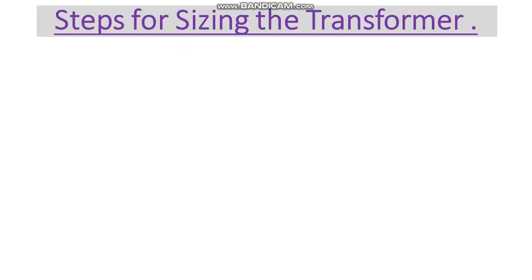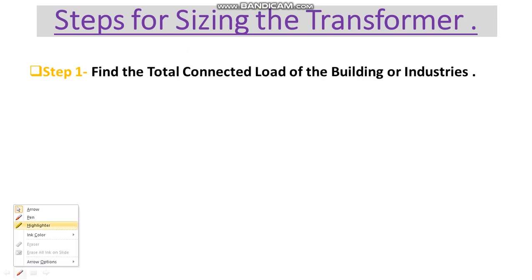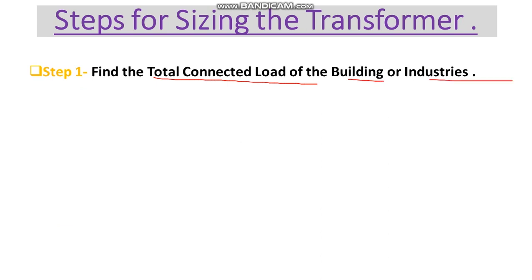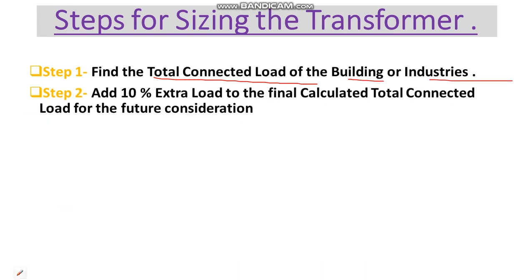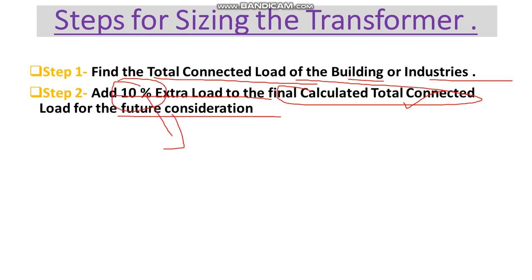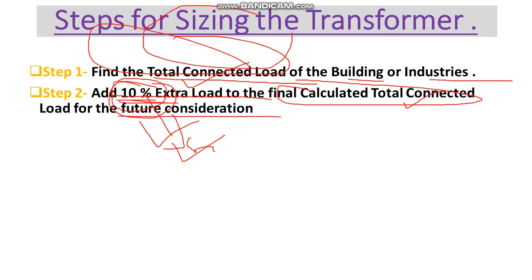Here we have some steps for sizing the transformer. In Step 1 we have to calculate the total connected load of the building or industry. In Step 2 we have to add 10% load to the final calculated total connected load for future considerations. This 10% is a safety factor, as we might increase our load in the future.